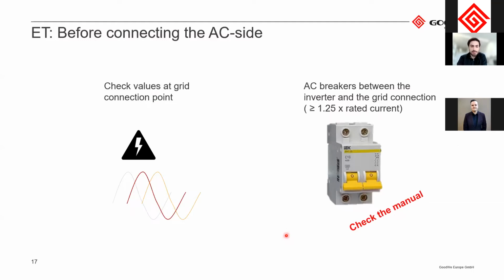Going forward to the AC side, before connecting anything to the inverter, please measure the values at the grid connection point to make sure that the inverter is compatible with the grid. Then also install AC breakers. This is really recommended from our side. Here you only see a one-phase AC breaker. In this case, you would need a 3-phase AC breaker.